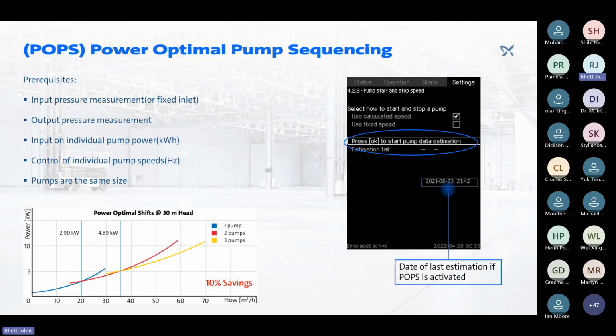And this is only really possible to get the best efficiency if you know the curve of your system. With Grundfos multi-pump controllers, this comes pre-programmed within the pumps, and you merely select the pump type, and it then knows the curve of the system and is able to control those pumps to the best efficiency point.